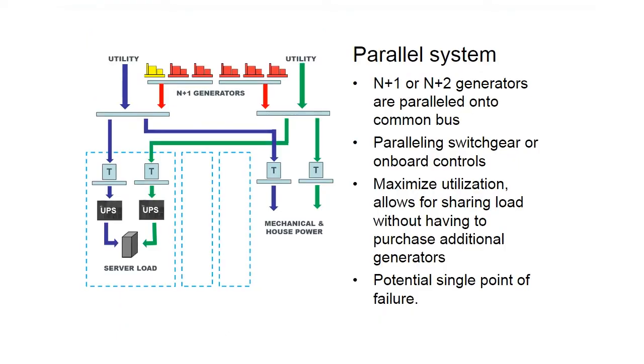Some examples of different distribution systems you'll see with mission critical data centers. A paralleled system, this is where there'd be generators connected to a paralleled bus, a common bus. Most of the time you'll see an N+1, N+2, so that if you lose one generator, there's a redundant generator to pick up, or if you have one out for maintenance for an extended period of time, you have an additional generator just in case.